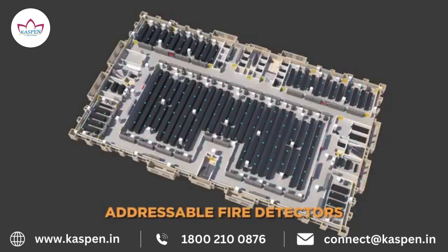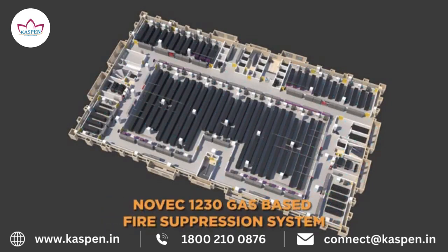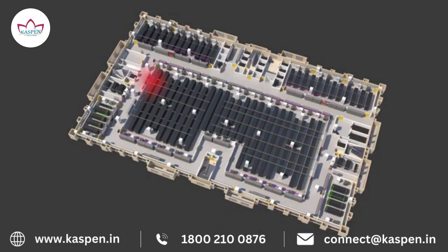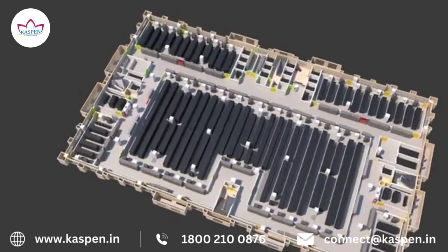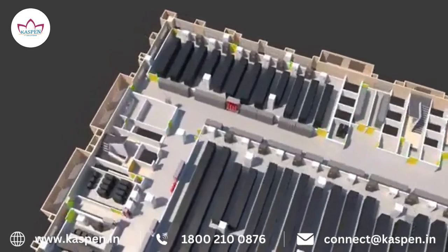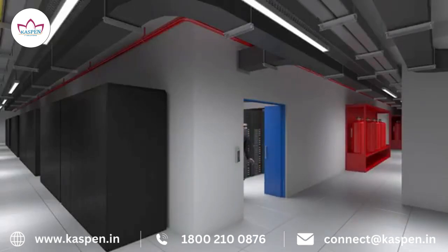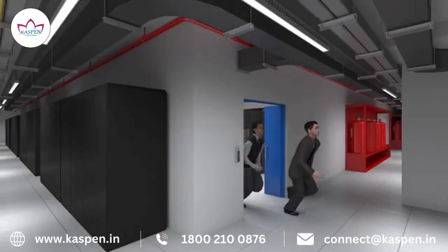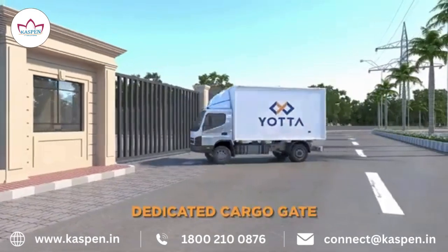Yotta NM1 is equipped with addressable fire detection and suppression system that can intelligently detect the exact point of fire. The fire detection system is also integrated with our access control system. In case of a fire, the access control system automatically opens the doors of the affected adjacent areas for quick evacuation. Cargo material enters the data center building through a dedicated cargo gate.